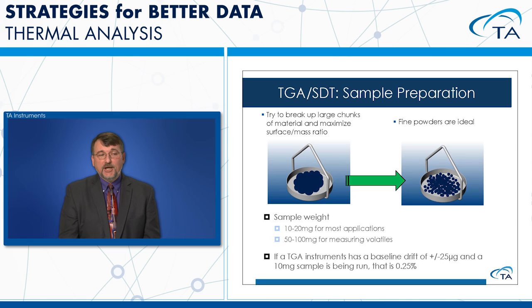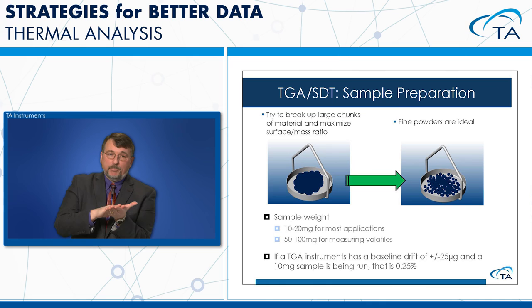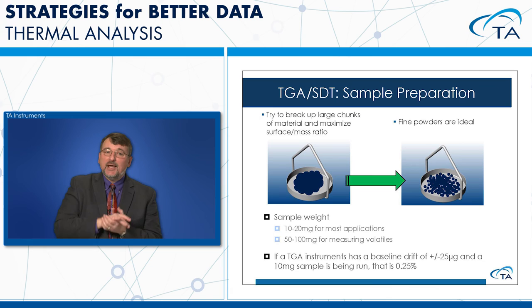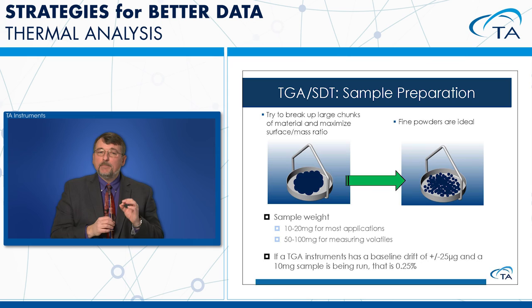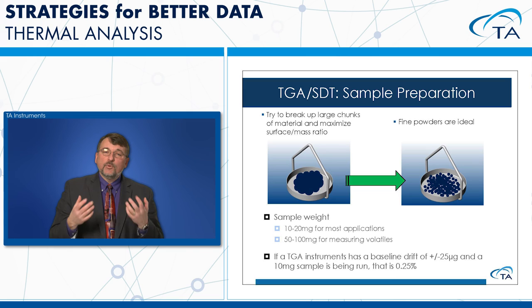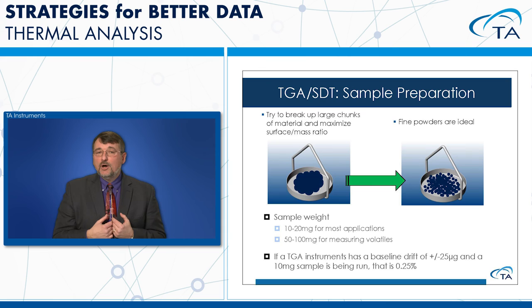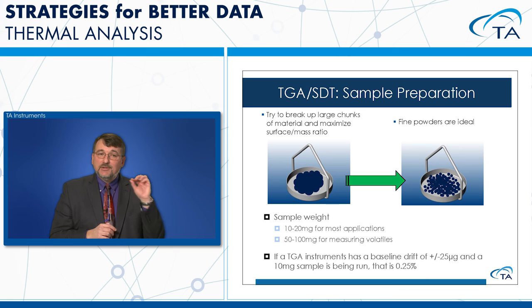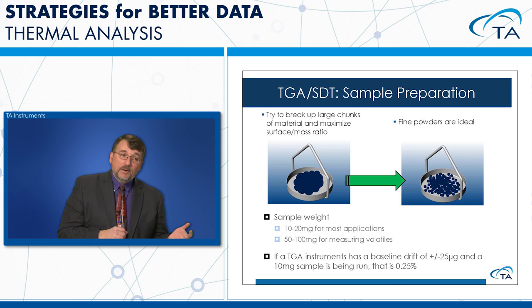For TGA sample preparation, the ideal sample is a powder spread evenly over the bottom of the pan. For large chunks or pellets, cut them into multiple small pieces and distribute them in the pan for better resolution. A typical sample weight of 10–20 mg works for most applications; larger samples of 50–100 mg are used when measuring very small volatiles. Always consider baseline drift: a 25-microgram drift on a 10 mg sample is 0.25%, but on a 1 mg sample it's 2.5%.